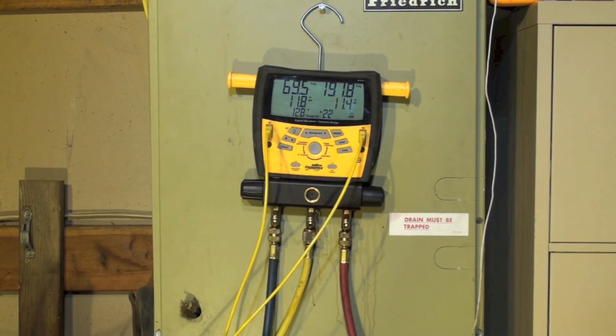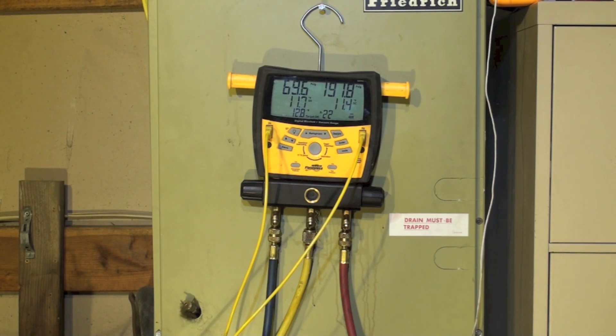After giving another 10 minutes or so for this to settle, I've added one ounce of refrigerant and we're down to about 12 and a half on the superheat. Target is 12.8 and subcooled around 11.4 which seems to be kind of normal for this thing. It does vary sometimes but it's pretty much normal.